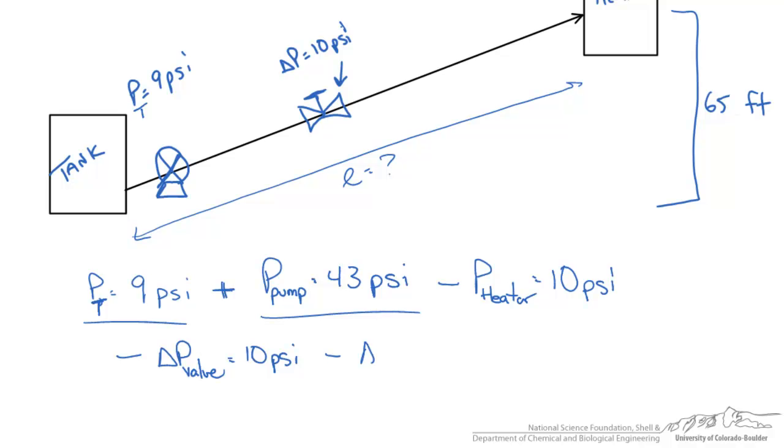We're also going to subtract out the losses due to elevation, delta p elevation. Based on our heuristic, our losses associated with elevation are 4 psi per 10 feet of elevation change. Since we're going up, these are going to be lost.